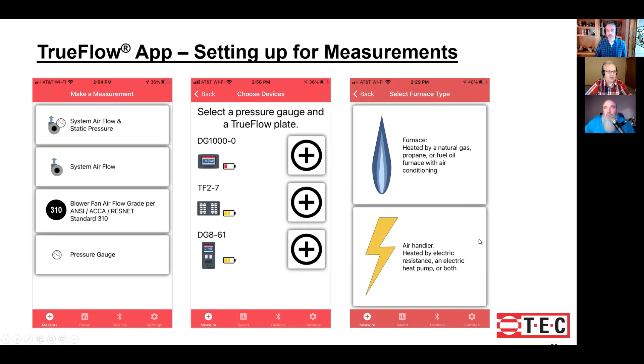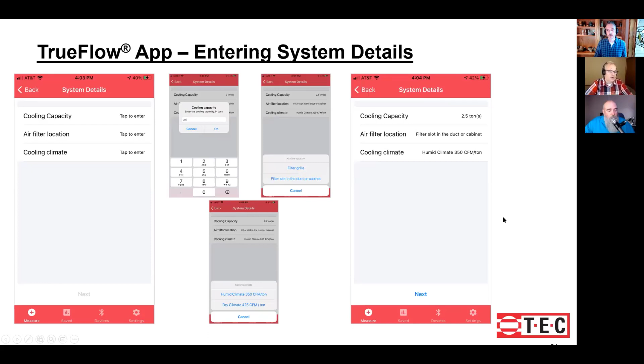Let's start with the static, the system airflow and static pressure. The next step is to connect to the devices. So you're going to connect to the TrueFlow grid itself, and then either a DG1000 or a DG8 manometer. And then you start giving it information about the system. So is it a combustion furnace or is it electric heat? That's the first question. So the next thing we do is we need to give it the cooling capacity, and we need to tell it where the filter is, whether it's in a filter grill or a filter slot. And then for now, we just have two cooling climates, either a humid climate where we target 350 CFM per ton, or a dry climate where we're targeting 425. And there's some overlap there, so don't worry too much if you're in one of the intermediate climates.